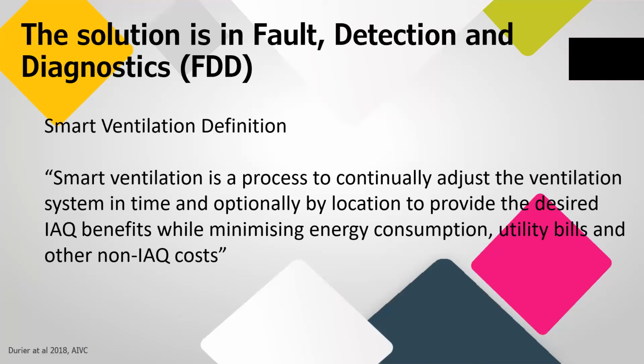So the sad truth is that what is meant to drive a smart ventilation system, your BMS, very often is unable to do so, or is sometimes corrected by manual modification of its standard operation to resolve complaints from the occupants of your building, or design defects that were created when the building was built.